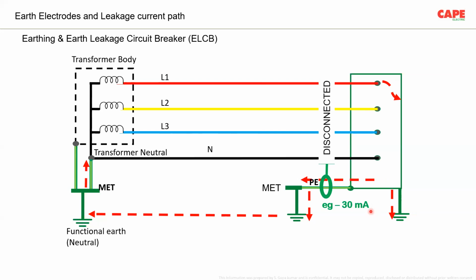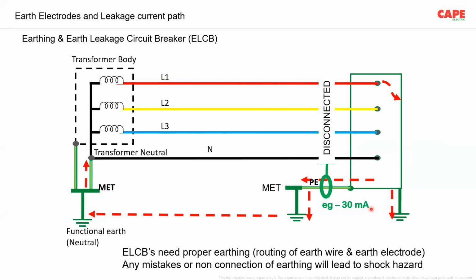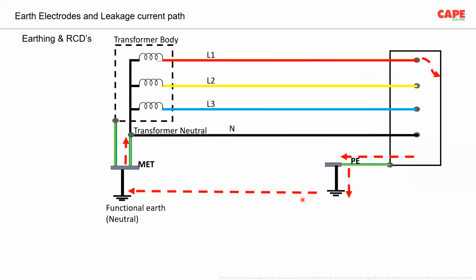But what you should understand is ELCBs are nowadays outdated. Nobody uses ELCBs in the market, or I don't think that they are available in the market. Nobody uses them, except some old installations. Now, what you should also understand is that for an ELCB, proper routing of the earth conductor and the earth electrode was important. However, currently, what we use for earth leakage protection or earth fault protection in a TT system is an RCD, a residual current device.